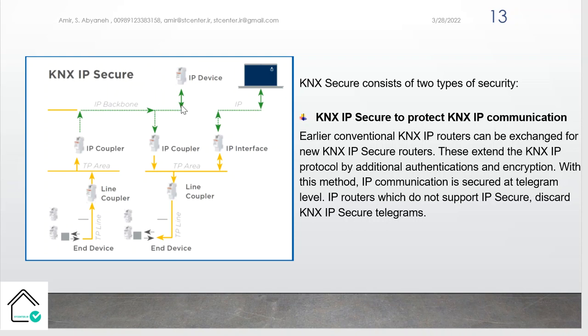KNX Secure consists of two types of security. First of all, KNX IP Secure to protect the KNX IP communication. Earlier conventional KNX IP routers that we are using nowadays can be exchanged for the new KNX IP Secure router. These extend the KNX IP protocol by additional authentication and encryption. With this method, IP communication is secured at telegram level. IP routers which do not support IP Secure discard the KNX IP Secure telegrams.